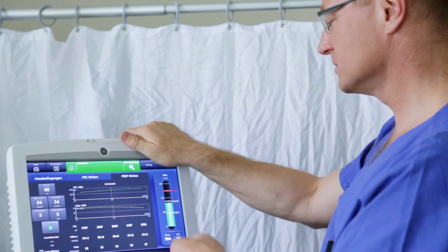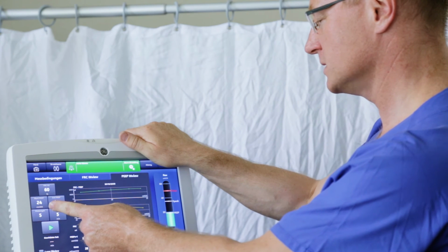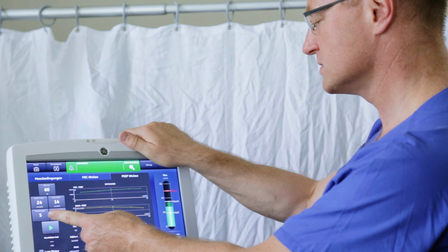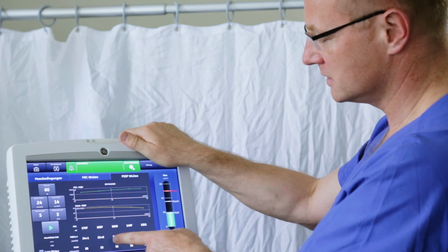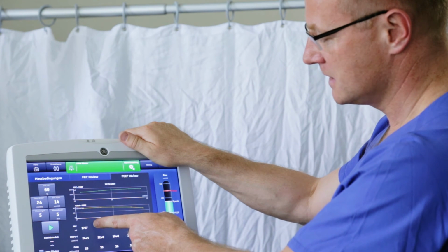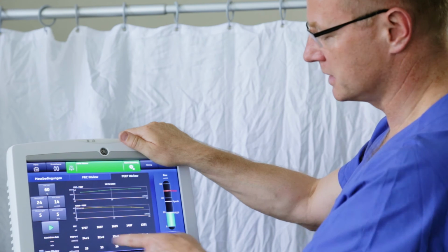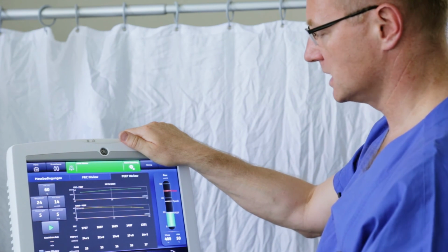The PEEP in-view measurement is now finished. Here we have our PEEP value with a start at 24, our end PEEP at 14, 5 measurements over a period of 5 minutes per level, and over there we can read the individual values for FRC, PEEP, and static compliance. At the top we see everything displayed again in the form of a graph.